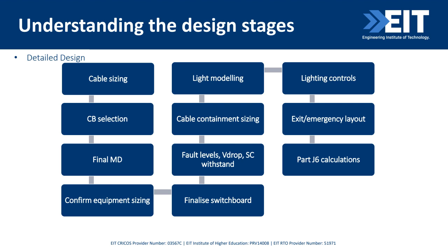But in general, we move through at a detailed design stage. So this is all of the design processes. We size our cables, which allows us to select our protective devices, our fuses and our circuit breakers. Because we have a final MD, we can confirm our equipment size. So how big is our switchboard? We can finalize that size. This then allows us to model our fault levels, our voltage drop, our containment.